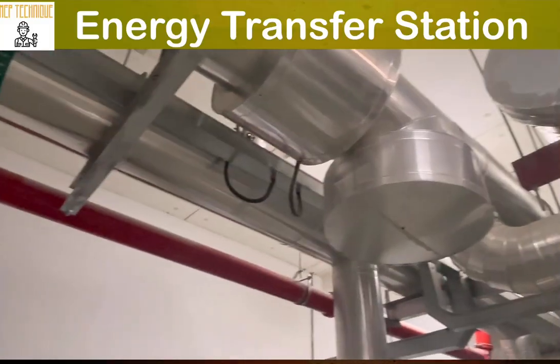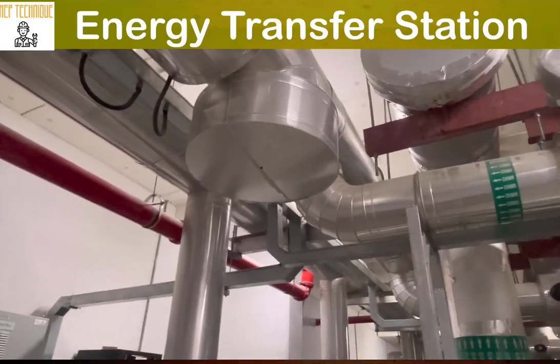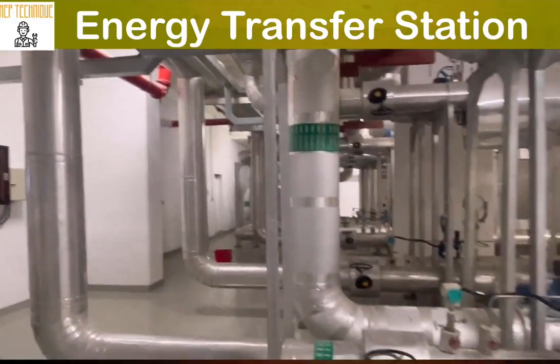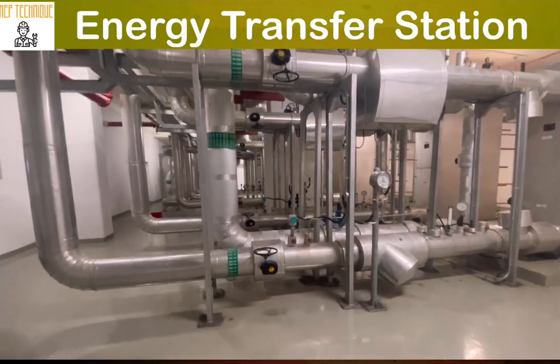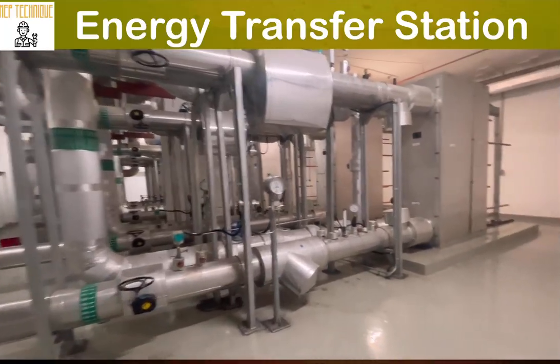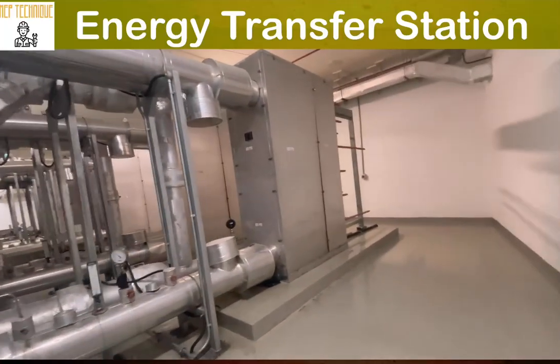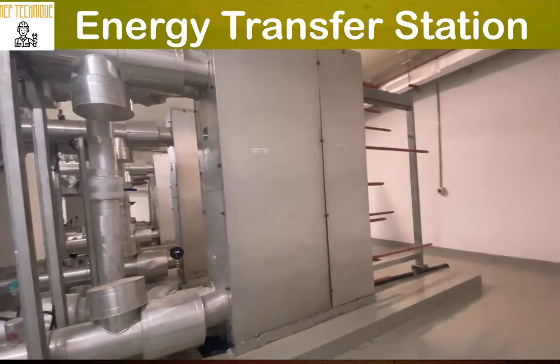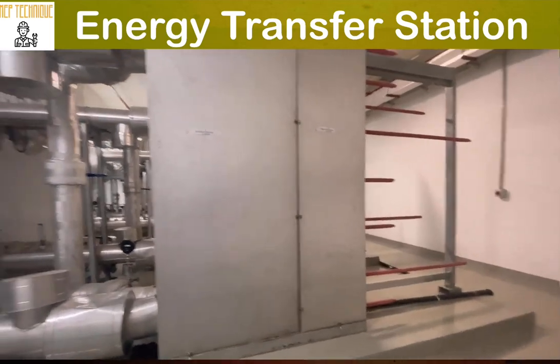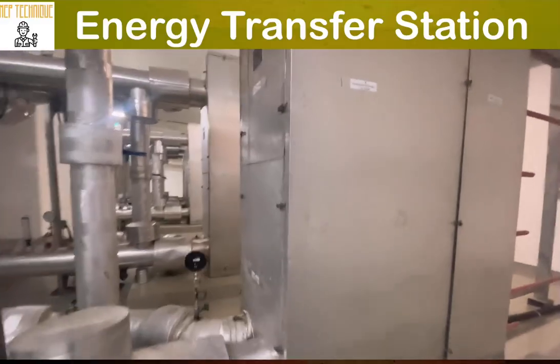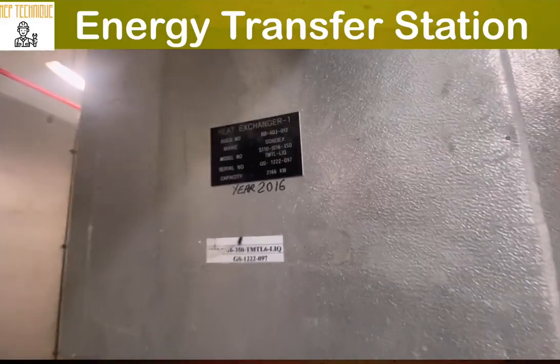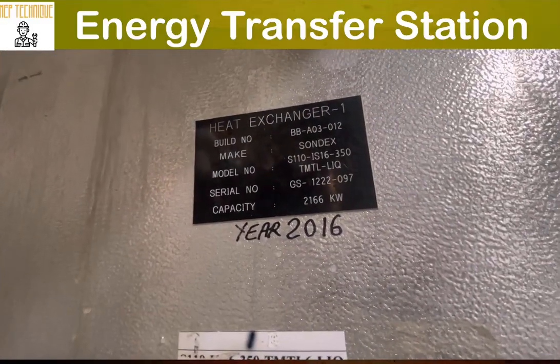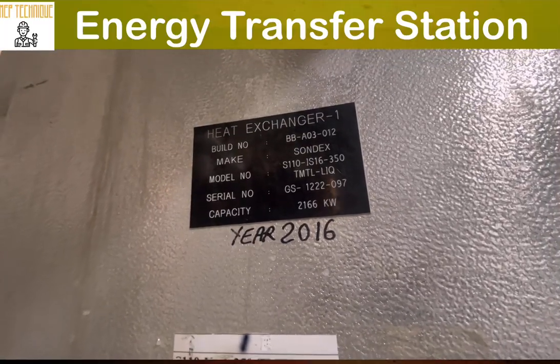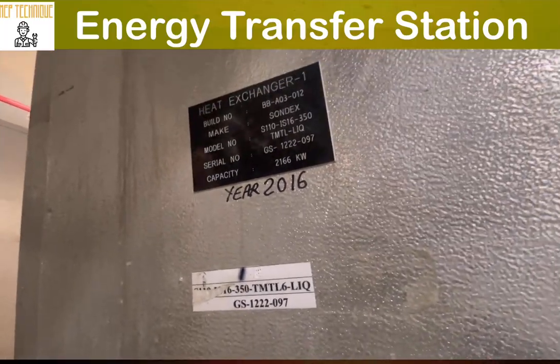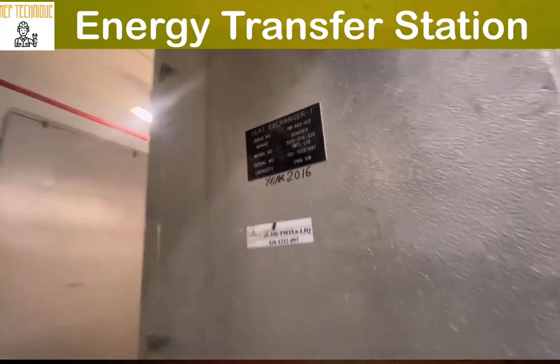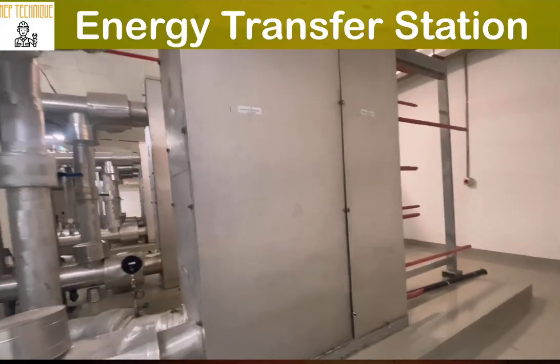The pipe came, and you can see there are lots of heat exchangers connected. In front of us there is a heat exchanger, and this is a plate type heat exchanger. So let us check the capacity. The capacity of the heat exchanger according to the manufacturer is 2166 kilowatt. So that means 616 ton. This is a 616 ton plate heat exchanger.